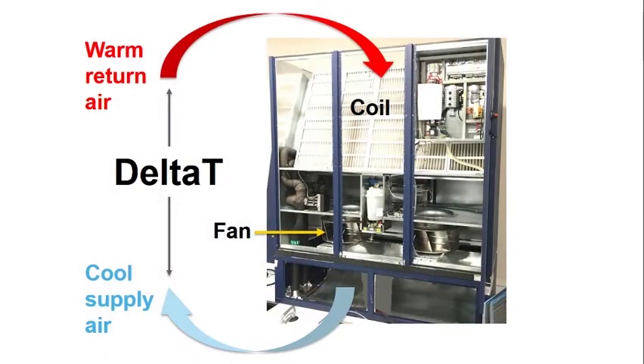Let's start with this slide that shows a picture of a cooling unit. You'll notice that the warm return air is coming up through the filter and then through the cold coil underneath. The hot air, once it goes through the cold coil, will come out cold at the bottom. The idea is to maximize the capacity of your cooling unit by increasing the temperature difference between the return and the supply air.